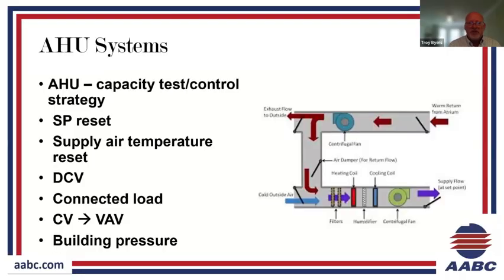We want to look at current sequences and try to determine if there's some energy saving opportunities as we go through basically a recommissioning effort, as we're looking at any existing system, to see if maybe we could employ a static pressure reset strategy. Looking at the static pressure in the duct if it's a variable air volume system, and the controls can poll each terminal unit looking at the damper positions. And if any damper is not at least 80, 90% open, then basically we have too much static for the given load conditions. And the static pressure set point can be reset downward incrementally until we see those terminal unit inlet dampers begin to open up more and relax that system. So now we're using less energy.